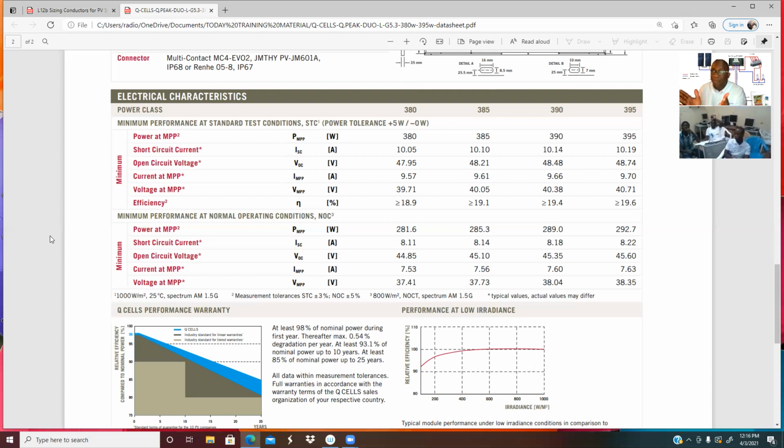It doesn't always happen, but it's possible that sometime, maybe in November when the sun gets very hot in Liberia, or anywhere in Africa, the sun could have a higher peak for about 3 hours in a given day. So they're saying that is the reason why you need to add another 1.25 for your conduit sizing.